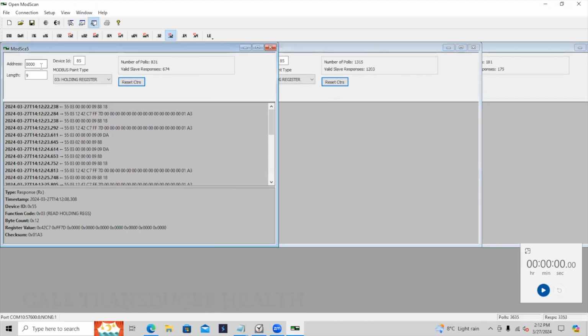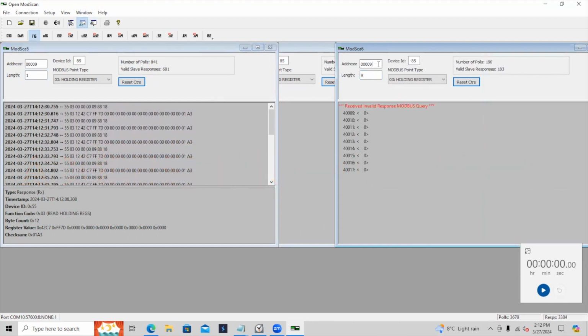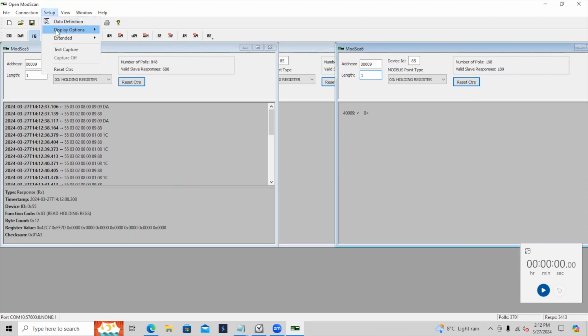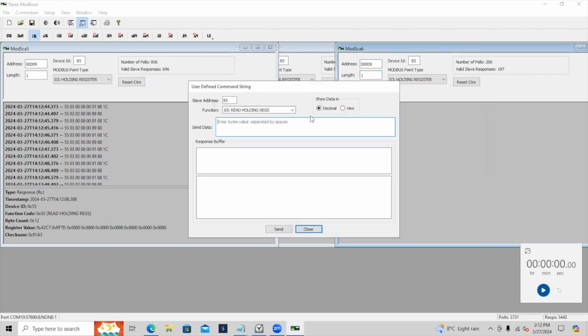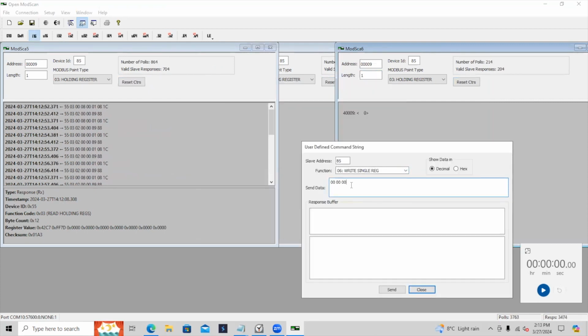In the example here, the address is 9, the length is 1. Over here, we've set up the 16-bit register. In this case, because there's only one single digit output, we're going to make the byte order little endian. We're going to go to our user message to set scan command, single write register, sending the 04 scan command. We can send it. And you can see immediately we have a number 5 coming out, showing that the sensor is now scanning. This will update as per the long data dump that we showed earlier.